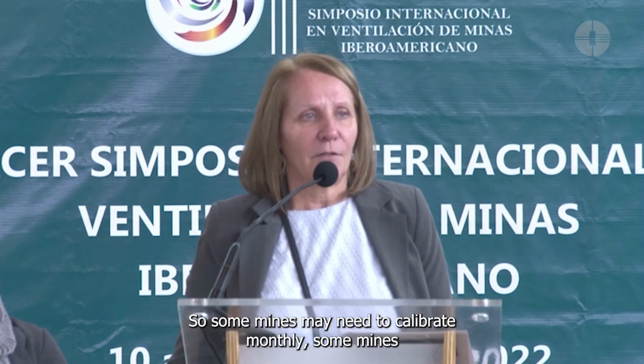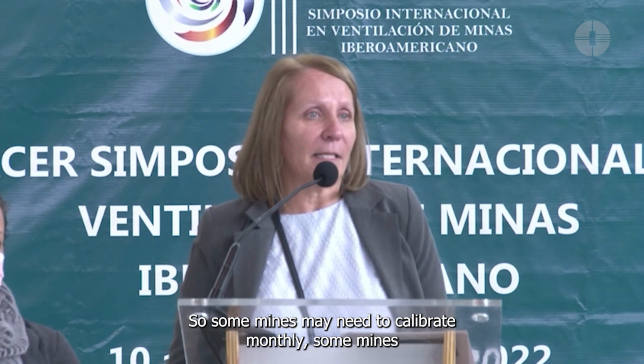So the maintenance of the calibration of the gas sensors themselves? Yes, so the calibration, we recommend that you start at every 3 months, but every mine environment is going to be different. Some mines may need to calibrate monthly. Some mines may only need to calibrate the gas sensors every 6 months. So it really depends, but we do suggest you start at a 3-month calibration period and then do a bump test on the gas sensors to see if they're still in calibration. That way you can gauge the time frame to do the calibrations yourself.